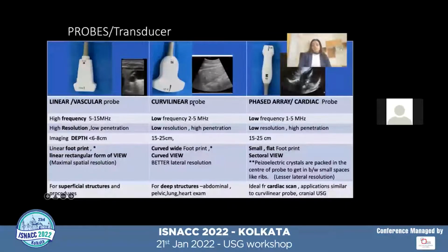This is the curvilinear probe. It is a low frequency probe with the frequency of 2 to 5 megahertz. Low frequency means low resolution and higher penetration. So depth achieved is 15 to 25 centimeters. It has a curved wide footprint with a curved view on the image, and it has a better lateral resolution.